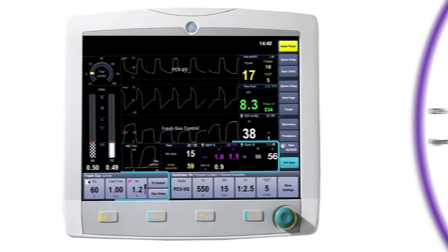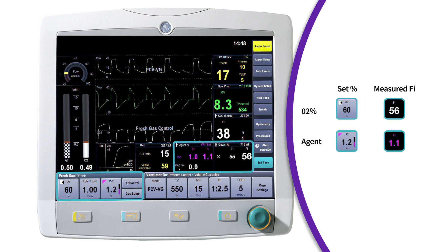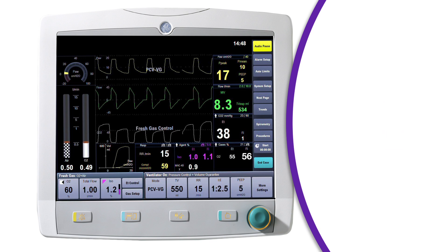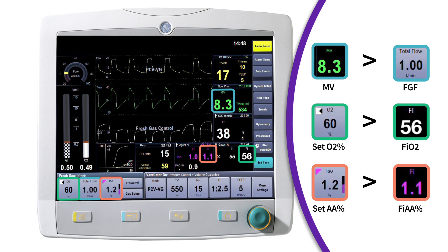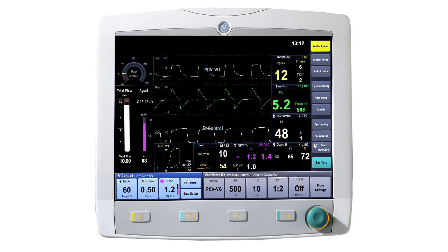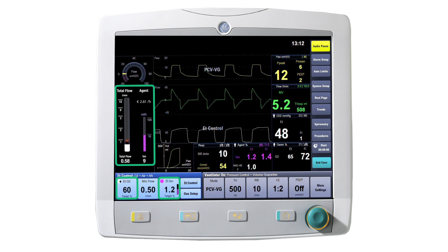End-tidal control also helps with knowledge gaps in circle anesthesia systems due to the dilution effect of rebreathing. With circle anesthesia systems, the greater the difference between fresh gas flow and minute ventilation, the greater the difference in set versus delivered concentrations of agent and oxygen. The end-tidal control algorithm automatically adjusts the fresh gas flows to meet the targeted end-tidal oxygen and anesthetic agent concentrations, taking into account the differences between fresh gas flow and minute ventilation.